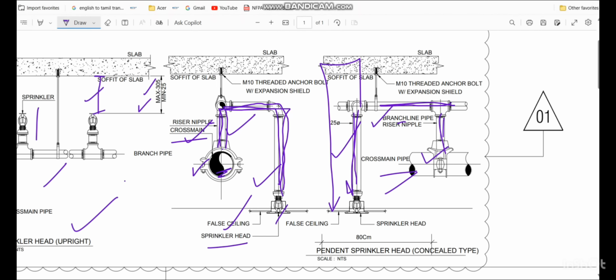If you are taking directly from down for the individual pipeline, the dust particle will block the sprinkler. So that is the reason for the cross main we have to take the return bend like this. For the coming to the branch pipe, you are already taking up. So that time no need separate return bend for each sprinkler. This is the important installation rule.